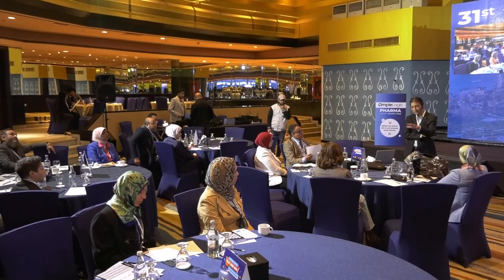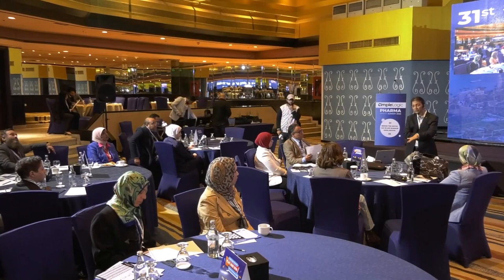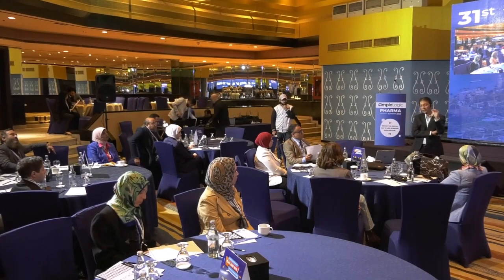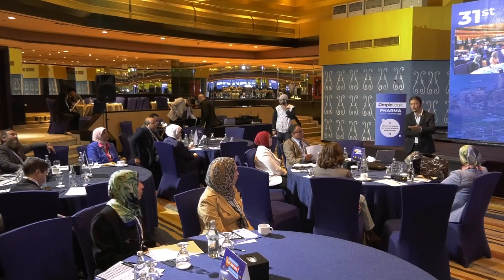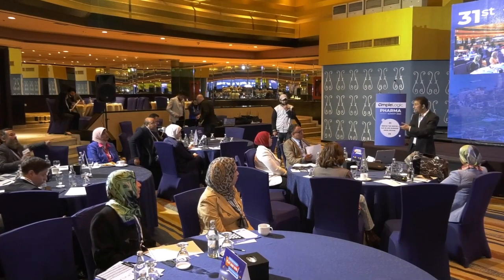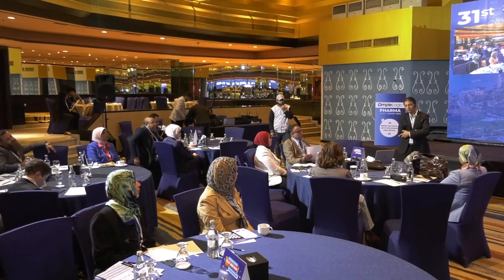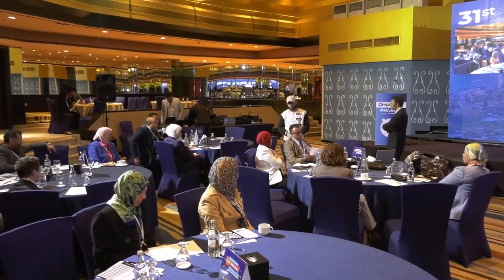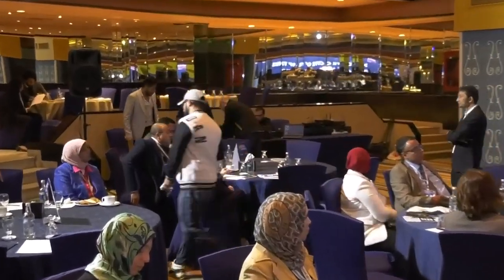Weighing the least weight will help me for the daily verification. And I agree that at some time point I have to do the calibration for the entire range, which can be monthly, or at any given time period. Regarding verification, the USP has said that it is a periodic check for balances, and the periodic check should be performed by two tests. The first one is the accuracy test, and the second one is the repeatability test.